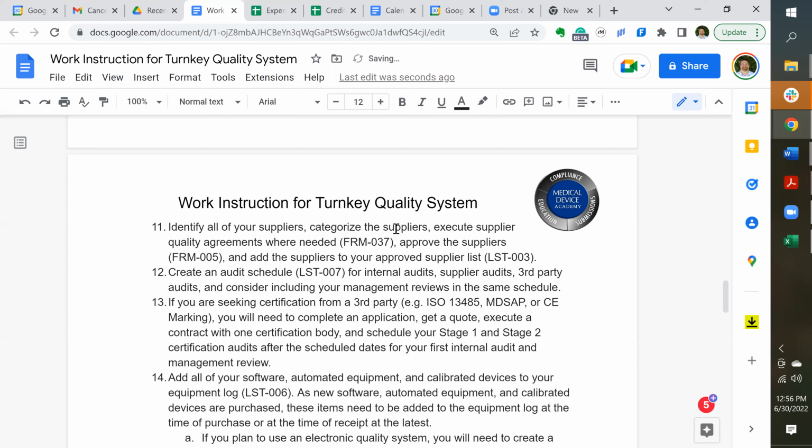So a subassembly, they're taking multiple off-the-shelf items and they're building them together for you. And they're maybe doing some tests. That would be a subassembly, like a printed circuit board. All the items might be off the shelf except the PCB. And then when you make it an assembly, now that's going to require process validation. It's going to require testing, and it's custom to your company. So that would be a crucial supplier. They're not a critical supplier because it's still just a component, but it's a crucial supplier because it's custom to your company. And so you should put them at a higher level of importance.